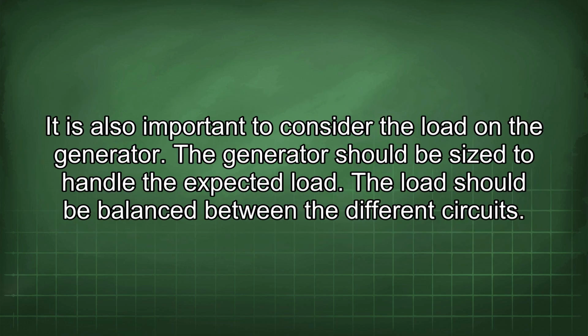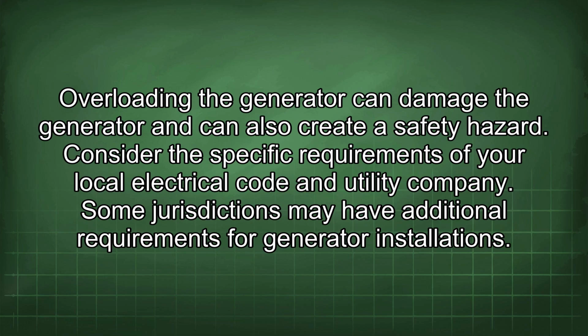It is also important to consider the load on the generator. The generator should be sized to handle the expected load. The load should be balanced between the different circuits. Overloading the generator can damage the generator and can also create a safety hazard.